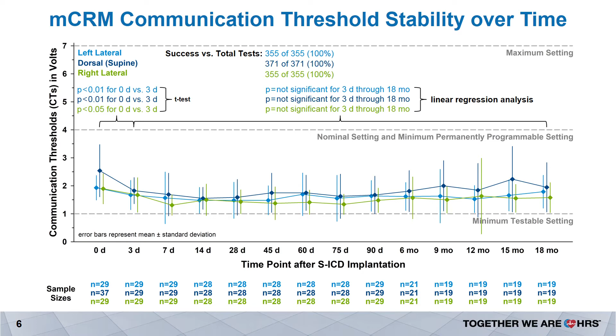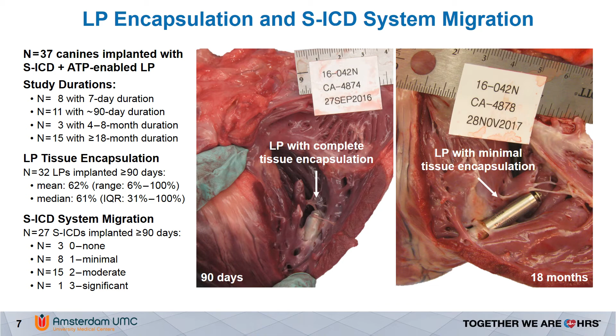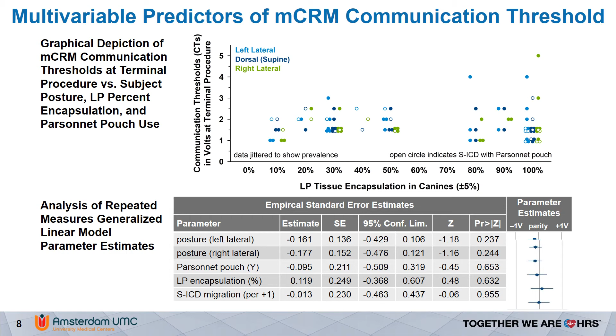The 37 canines were implanted with a follow-up time ranging from 7 days to 18 months. LP tissue encapsulation ranged from 6% to 100%, with mean and median values around 60%. The SICD system was not designed for canine subjects, and their looser skin and posture and activity differ significantly from the human implants. mCRM communication thresholds for each posture at termination procedures versus LP tissue encapsulation and Parsonnet pouch use are depicted graphically on the upper graph. No statistically significant influences on mCRM communication thresholds were observed for subject posture, Parsonnet pouch use, percentage of LP tissue encapsulation, or SICD system migration.